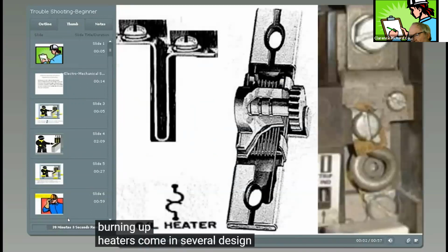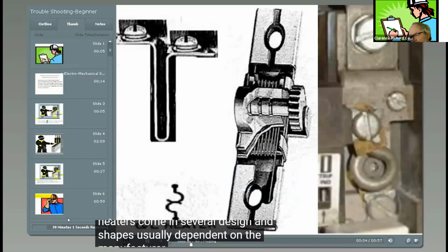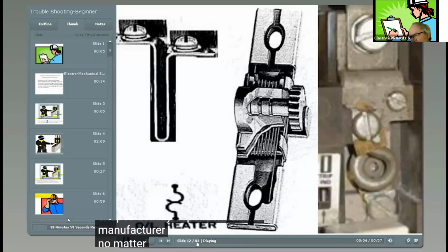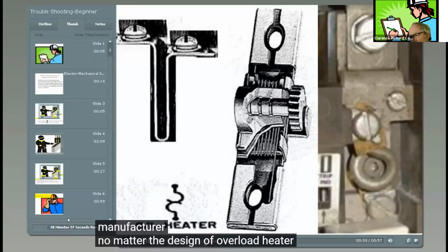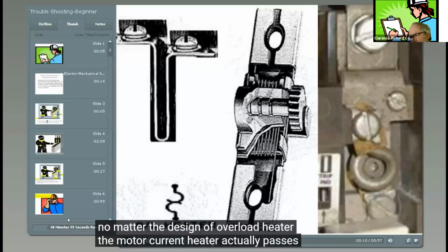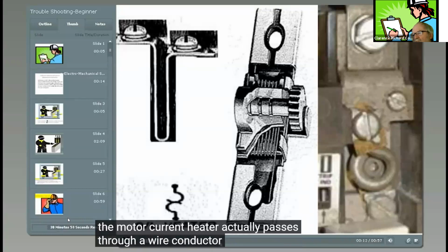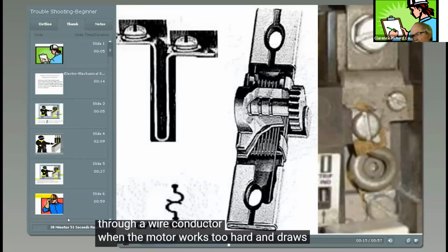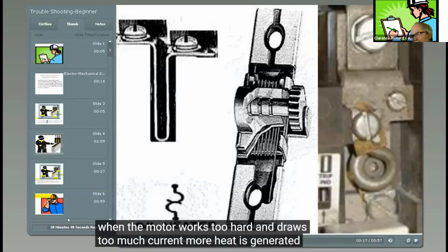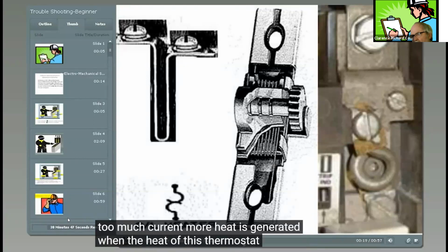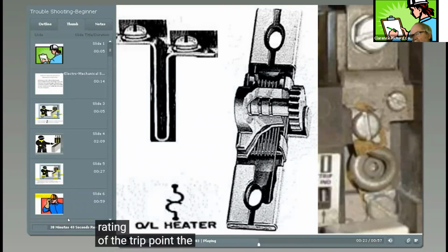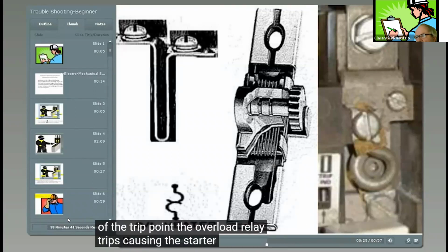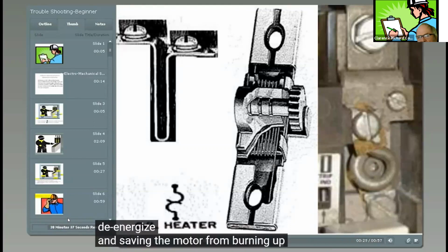Heaters come in several designs and shapes, usually dependent on the manufacturer. No matter the design of the overload heater, the motor current actually passes through a wire conductor. When the motor works too hard and draws too much current, more heat is generated. When the heat at this thermostat exceeds the trip rating, the overload relay trips, causing the starter coil to de-energize and saving the motor from burning up.